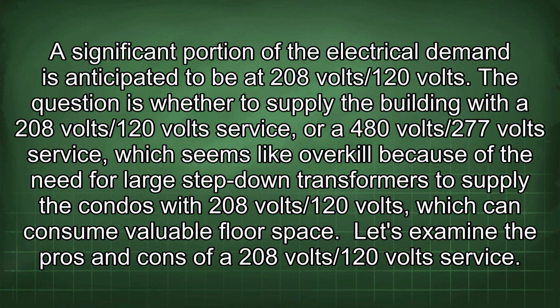A significant portion of the electrical demand is anticipated to be at 208 volts/120 volts. The question is whether to supply the building with a 208 volts/120 volt service or a 480 volts/277 volt service, which seems like overkill because of the need for large step-down transformers to supply the condos with 208 volts/120 volts, which can consume valuable floor space. Let's examine the pros and cons of a 208 volts/120 volt service.